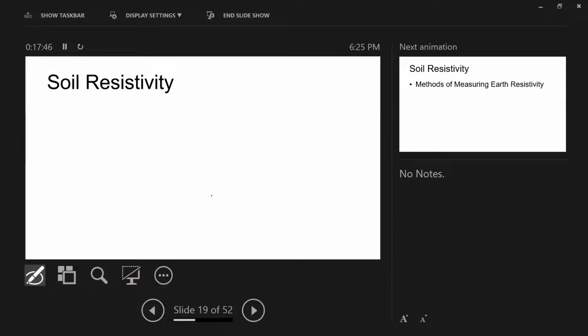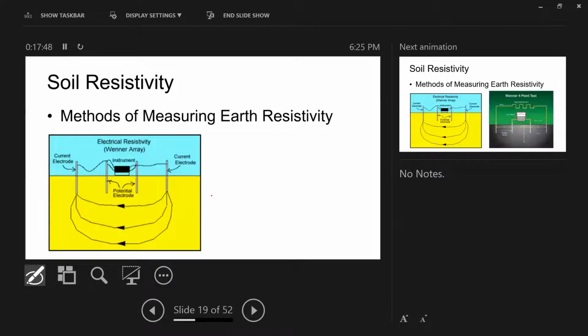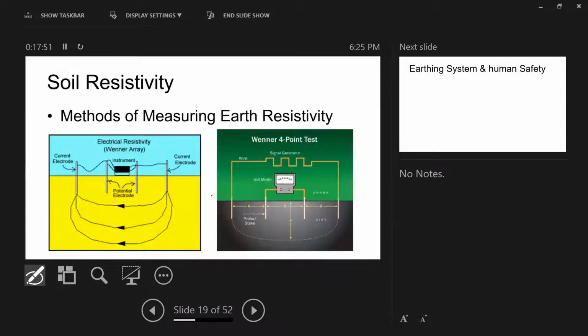Now, from all this, we need to understand the soil resistivity. How do you measure the soil resistivity? By injecting current and measuring voltage. This is known as the Wenner method. With the Wenner method, the farther out you go, the deeper the current goes in. You need to check whether you have a low soil resistivity on top or at the bottom, because you want to know whether you have to drive your electrode deep into the ground. Maybe in the ground there is marble, and you will see there is a high soil resistivity. Then you will run your earthing system horizontally. Otherwise, you take it deep into the ground.